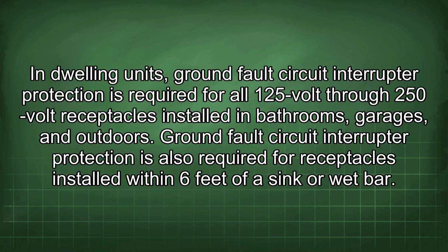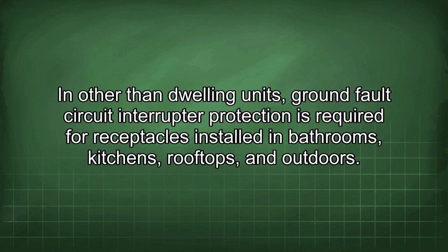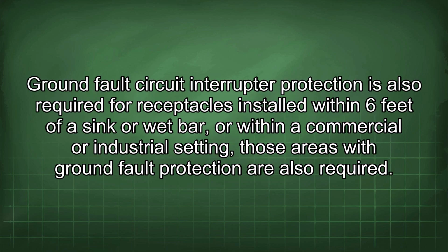In dwelling units, ground fault circuit interrupter protection is required for all 125-volt through 250-volt receptacles installed in bathrooms, garages, and outdoors. Protection is also required for receptacles installed within 6 feet of a sink or wet bar. In other than dwelling units, ground fault circuit interrupter protection is required for receptacles installed in bathrooms, kitchens, rooftops, and outdoors. Protection is also required for receptacles installed within 6 feet of a sink or wet bar, or within a commercial or industrial setting.